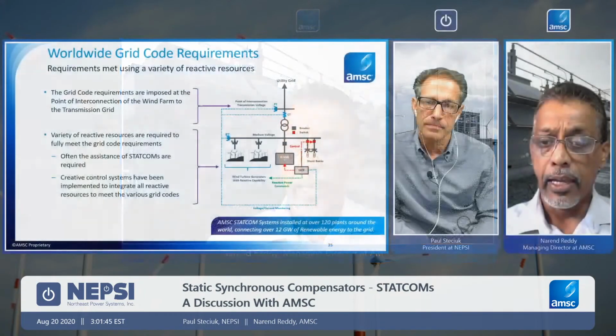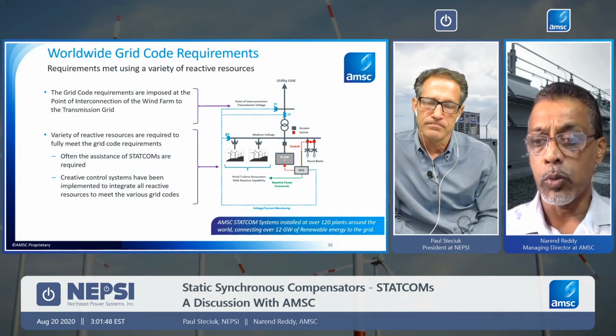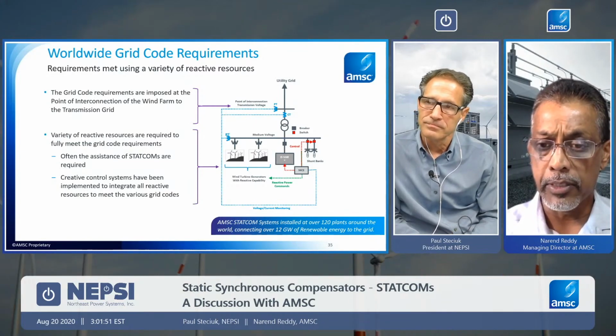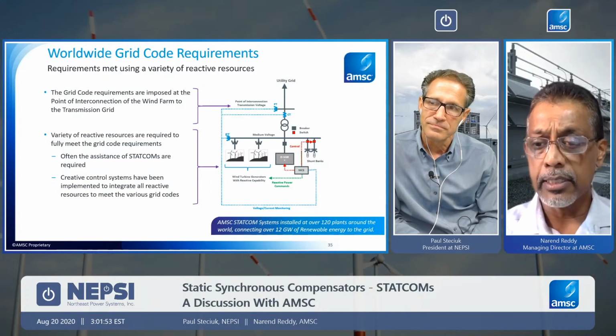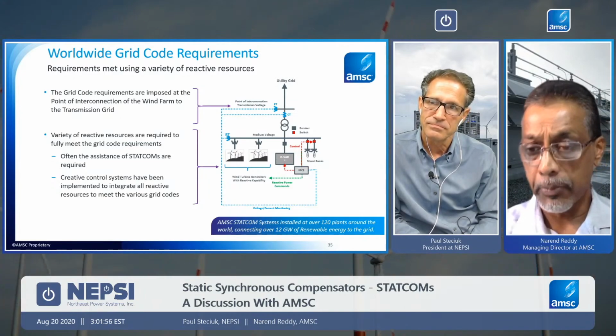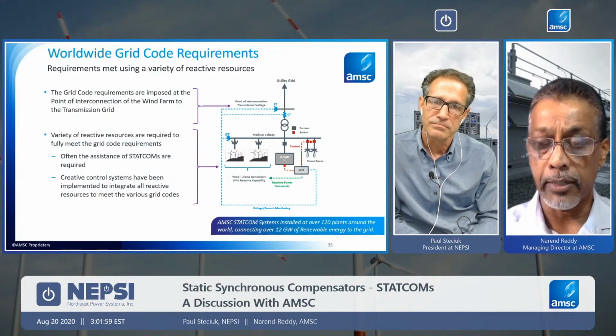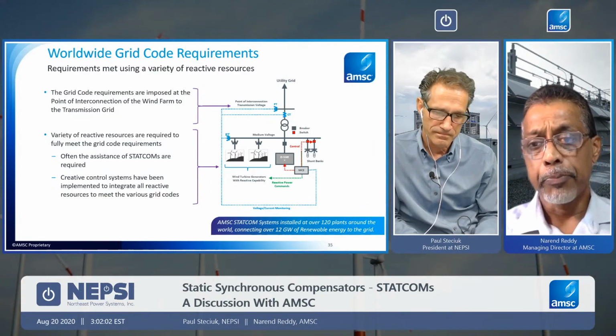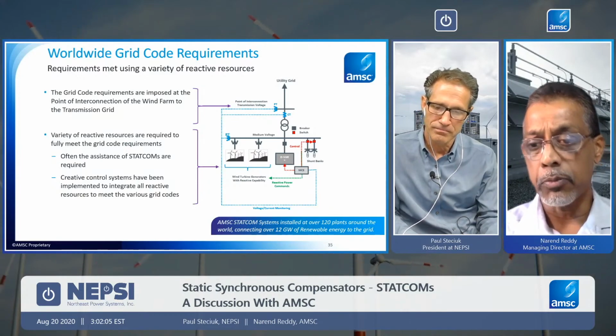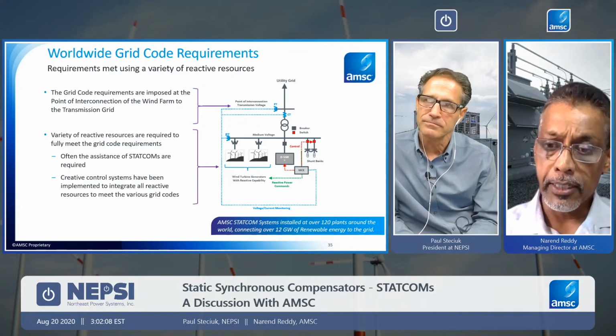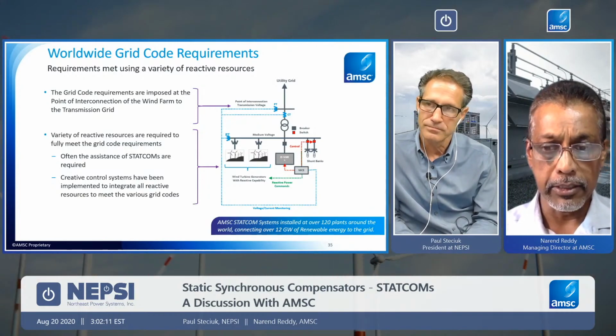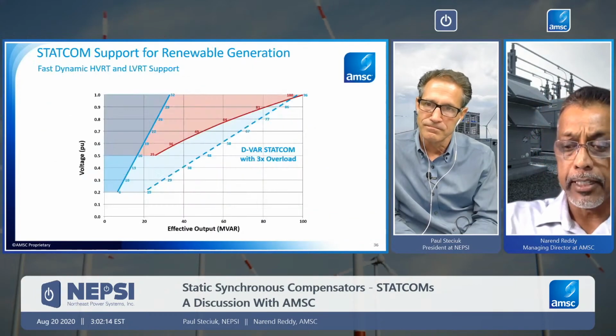The DVAR system would take care of all of the balance of plant control capability in terms of reactive power, voltage management, and grid support functionality, right at the substation level. And of course, depending on what sort of gaps are there in terms of the reactive capability, there might be steady-state power factor requirements. And this is where shunt capacitor banks, like the ones that you would supply and we've supplied together with NEPSI, come in for the steady-state compensation. The DVAR takes on the role of doing the faster regulation and faster mitigation. That's all.